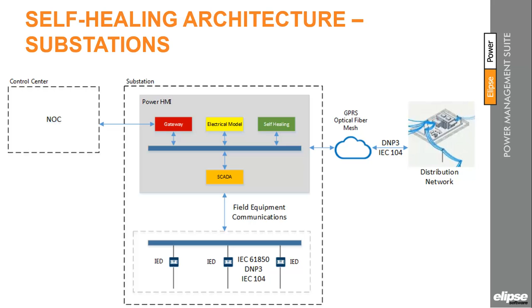The self-healing can be operated under two distinct architectures. The first refers to the model inside the Elipse Power HMI solution. In this case, it is possible to perform network recovery by connecting to distribution devices through protocols like DNP3 or IEC 104, using fiber optics or GPRS networks. This is a more viable setting for systems that already have contingency sites and local operation, with communication to the control center made by the gateway interface at Elipse Power HMI.